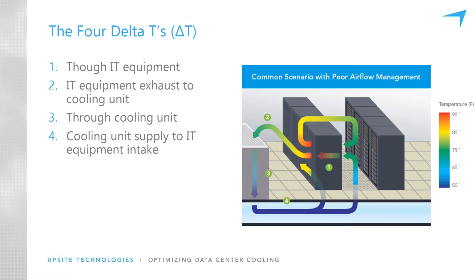The exhaust air coming out of servers is easily around 100 degrees, so why is the return air temperature at the cooling units often around 70 degrees? Why is delta T2 30 degrees — 30 degrees colder from the time it left an exhaust to returning to the cooling unit? The answer is bypass airflow: extra conditioned air that didn't flow through IT equipment. Cool air from unsealed cable openings mixes with exhaust air and cools it off, or excess cold air from a cold aisle or a misplaced supply tile mixes and reduces the exhaust air temperature. The only way to reduce this delta T2 is to reduce the flow rate through the cooling units relative to the flow rate through the IT equipment.